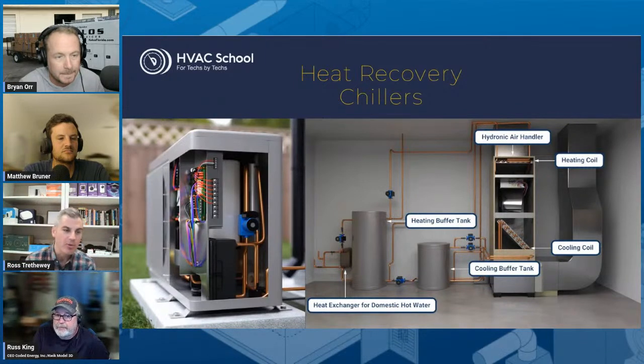Yeah, I was going to say, it depends on what kind of system we have, for what aux heat we have. If it's natural gas, we might be actually setting an outdoor temperature because we're concerned about the economic balance point, and it's more cost effective to run the natural gas than run the heat pump. But if we're talking about electric strip heat, that's a completely different situation. In that situation, we may be just based on time and temperature, based on the thermostat, where the heat pump is the first stage of heat, and it's going to try to do its thing. And if it can't keep temperature in the condition, we're still going to let it run, and we bring on the electric strip heat as backup.